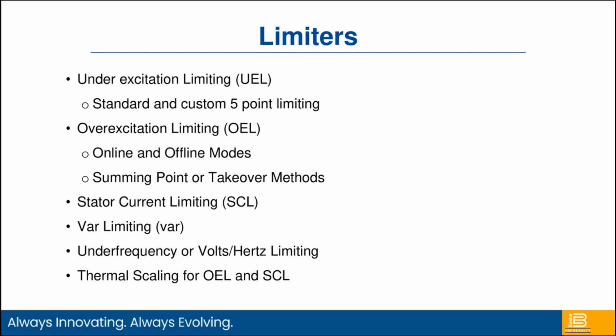And then we have our under frequency or volts per hertz limiting. We can also scale these based upon temperature. So we can do thermal scaling for our over excitation limiter and stator current limiter, which could allow us to increase the output of that particular machine if my ambient temperatures are low enough to handle the heat dissipation.